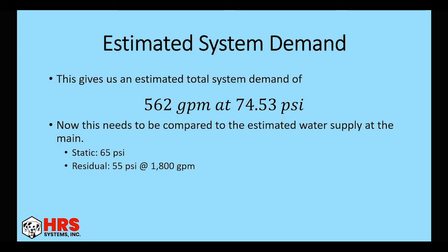So our total system demand at this point is 562 GPM at 74.53 PSI. Now, again, this is an estimate and I tried to go worst case scenario so that we could add more fittings. Pressure loss or the pressure demands might change a little bit. Our water supply might change a little bit. So we're trying to include several of those things by taking the worst case scenario.